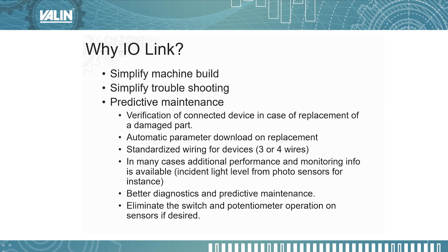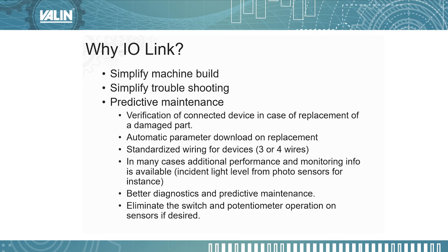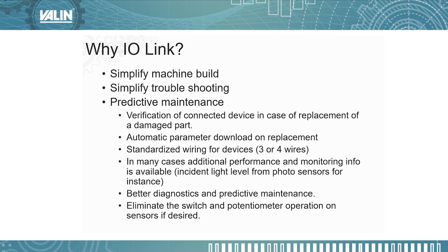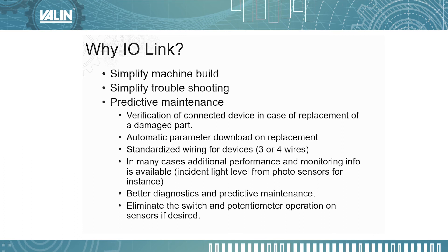You get better diagnostics and predictive maintenance features with all of those capabilities, and you can also eliminate unwanted potentiometer adjustments on sensors. If a device has a screw potentiometer that can be adjusted with a screwdriver, most IO-Link devices have a setting where you can specify that you want to ignore that potentiometer and only use the settings sent from the controller — keeping operators from going out and inadvertently tweaking those settings.